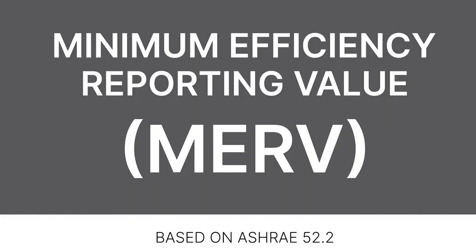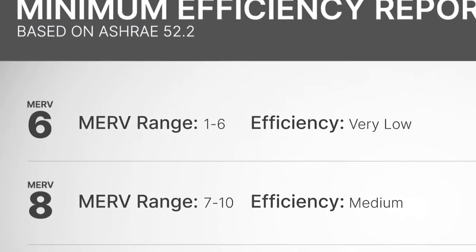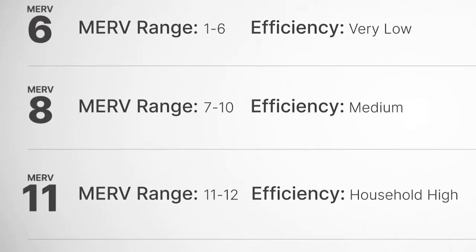And finally, that brings us to MERV rating. Short for minimum efficiency reporting value, the goal behind MERV was to give a standardized numerical value to the filtering ability of air cleaners. Ranging from 1 to 20, the lower the number, the less efficient. The higher the number, the more it will catch.